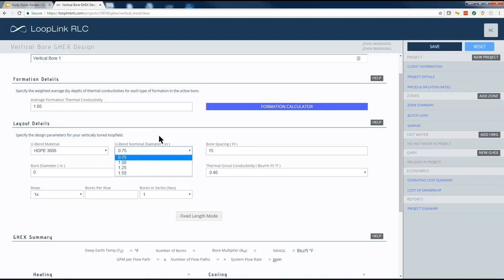U-bend diameter, basically when you design a ground loop, you're balancing all these different concepts at the same time as you make these decisions. You want to be able to balance flow in your loop field. You want to be able to achieve turbulence without excessive head loss, so that we maximize heat transfer in the ground loop without paying for a whole lot of pumping penalty.